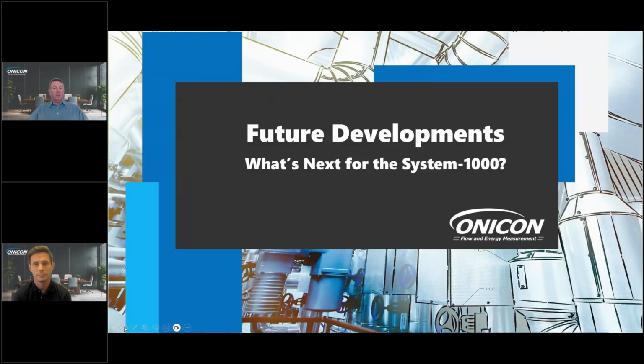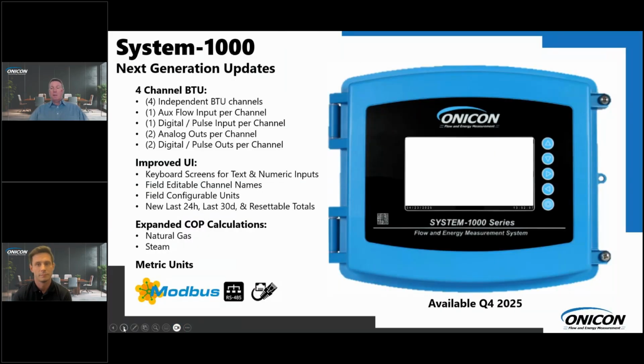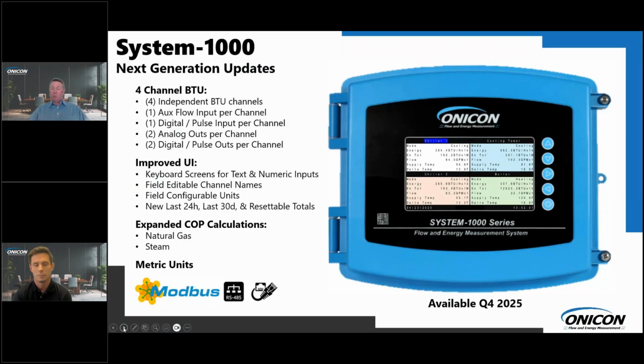So next we're going to cover the future developments for the System 1000. At ONICON here, we like to continue the growth of our products to help our customers in the field. The next generation of the System 1000 that's going to be available in Q4 of 2025, we're going to release as a 4 fully independent BTU channel system. Along with those 4 independent BTU channels, each channel will have 1 auxiliary flow input per channel, 1 digital pulse input per channel, 2 analog outs per channel, and 2 digital or pulse outs per channel.